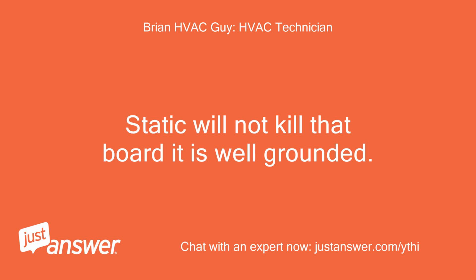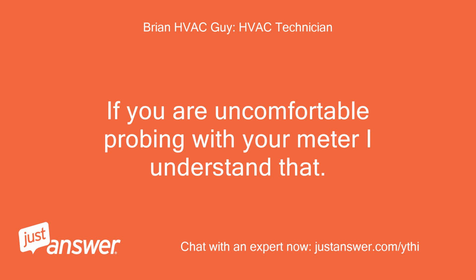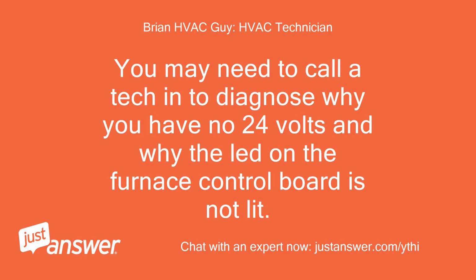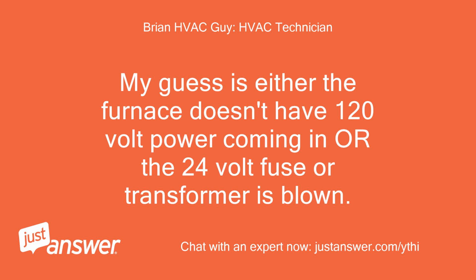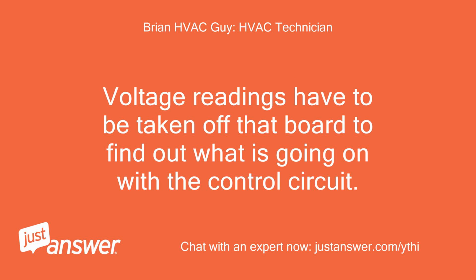Static will not kill that board, it is well grounded. If you are uncomfortable probing with your meter, I understand that. You may need to call a tech in to diagnose why you have no 24 volts and why the LED on the furnace control board is not lit. My guess is either the furnace doesn't have 120 volt power coming in or the 24 volt fuse or transformer is blown. Voltage readings have to be taken off that board to find out what is going on with the control circuit.